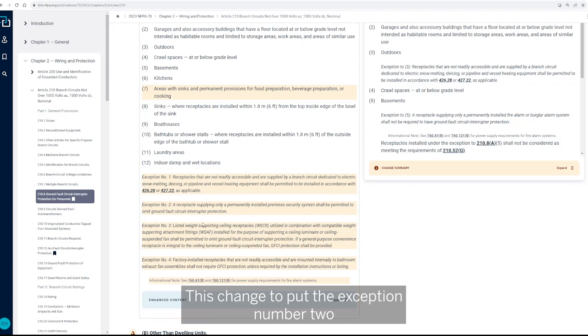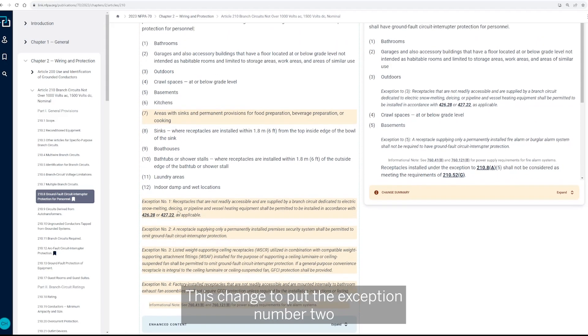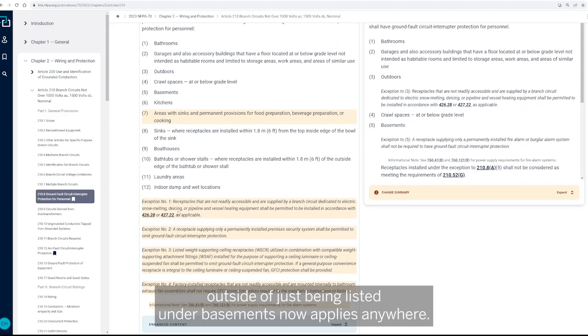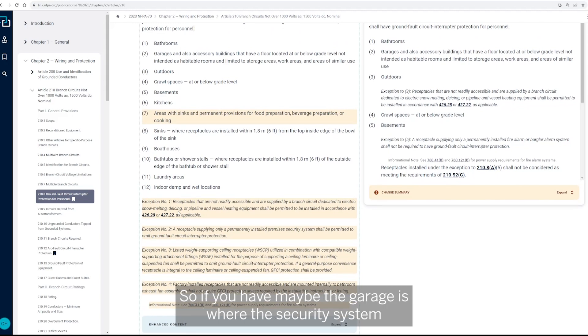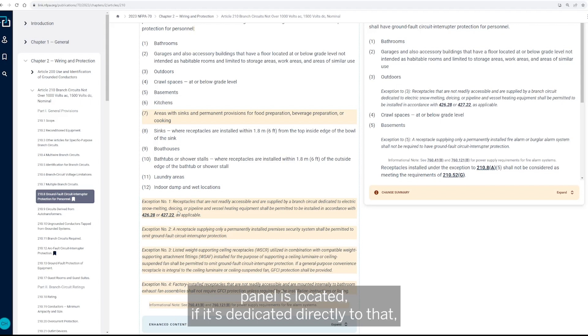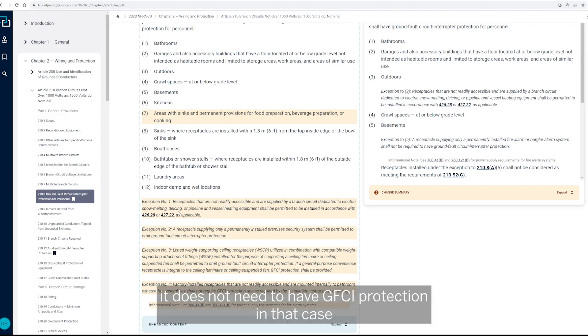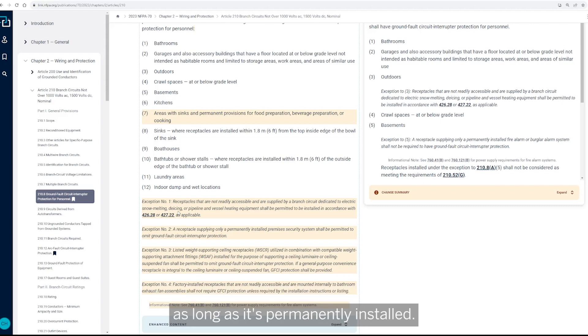Now this change to put the exception number two outside of just being listed under basements now applies anywhere. So if you have maybe the garage is where the security system panel is located, you know, if it's dedicated directly to that, it does not need to have GFCI protection in that case, as long as it's permanently installed.